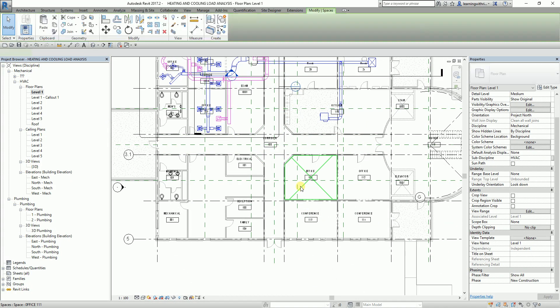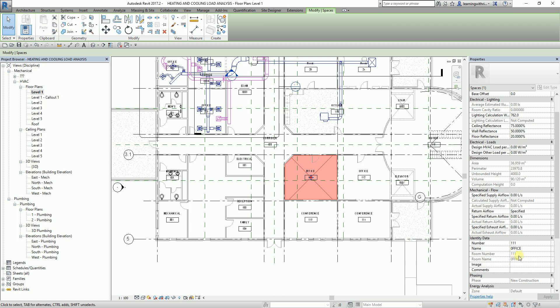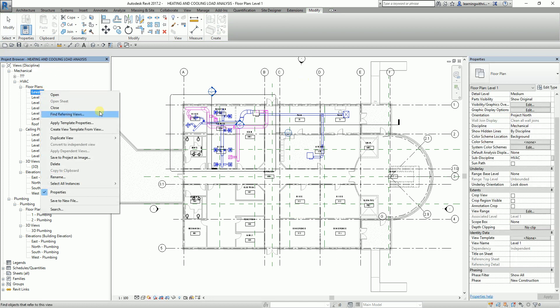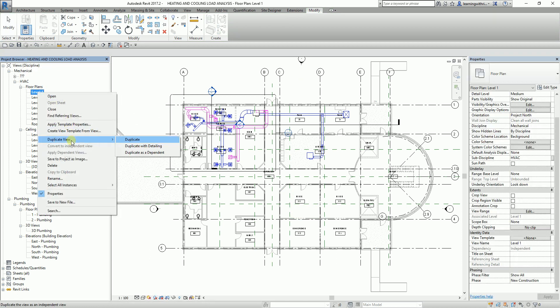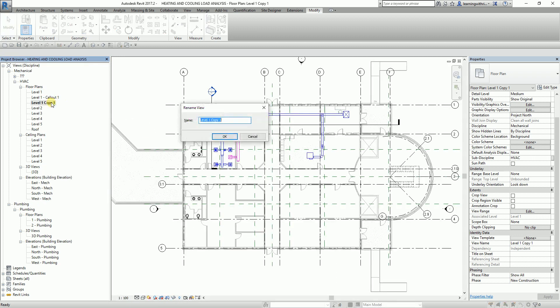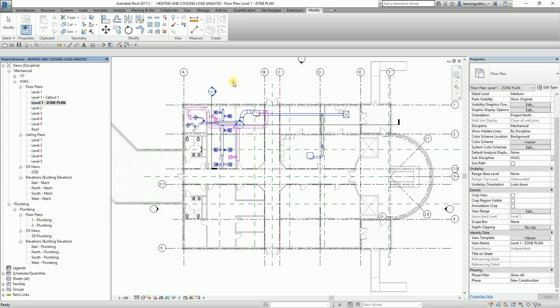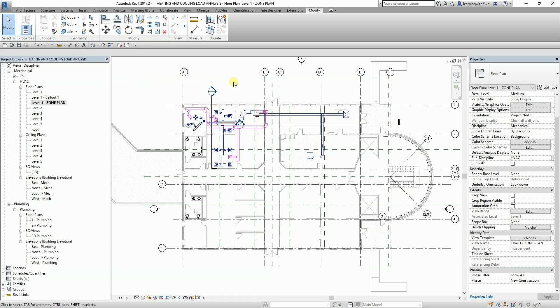Now after we change the names of our spaces based on the room number and room name, I'm going to duplicate this view and rename it — let's call this Zone Plan. In Revit, you can create zones that represent areas served by one piece of mechanical equipment. Properly defined zones allow you to size the equipment based on the cumulative information of the spaces grouped within a zone. Each zone contains information about heating and cooling temperatures and outdoor air, which Revit uses during the heating and cooling loads analysis to determine the energy demands of the building.